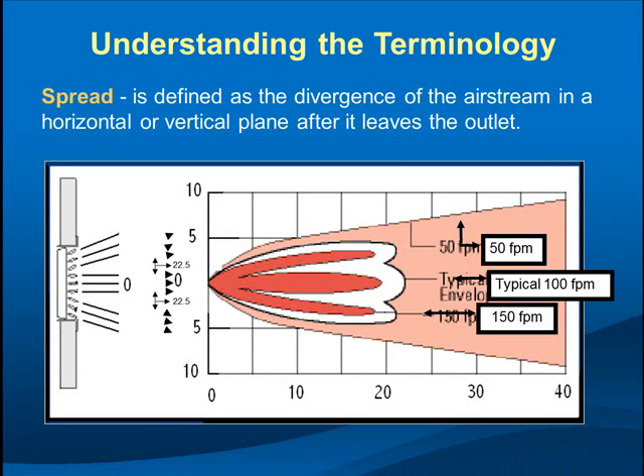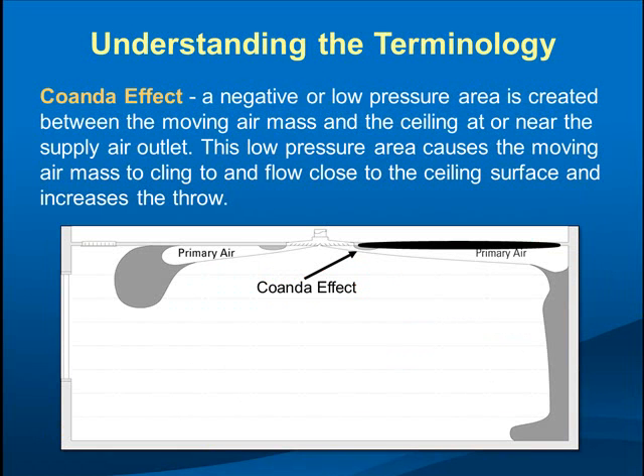Spread is typically used for grills. We talk about adjusting the blades in the grills, and we give the throw at several different grill blade spacings so you can see how much throw is reduced as you increase the spread. We only talk about spread for grills with deflections in the front.